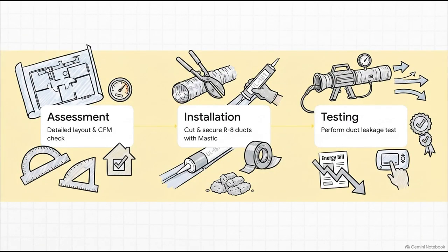Here's how those steps come together. First, the detailed assessment of your layout and CFM. Second, the precision cutting and securing of those R8 ducts with the UL 181 mastic. And third, so absolutely vital, we perform a rigorous post-installation duct leakage test, actually testing our own work before we finish up to guarantee you have proper, perfectly balanced airflow. When we're done, your energy bills are going to drop and your HVAC system will finally work exactly the way it was engineered to.